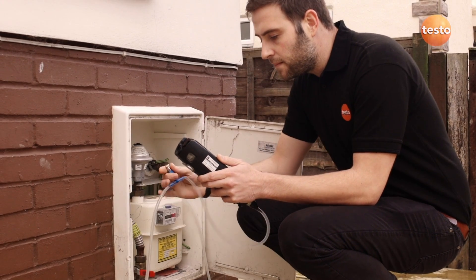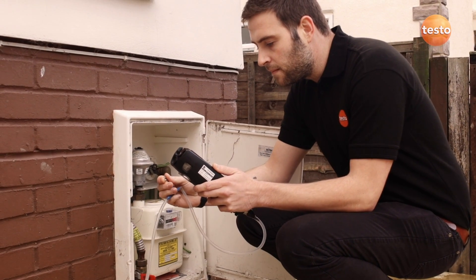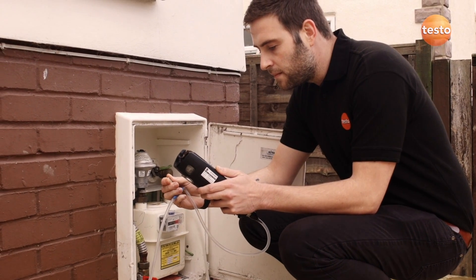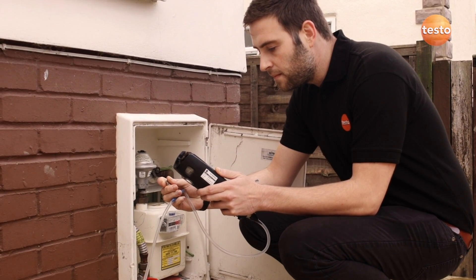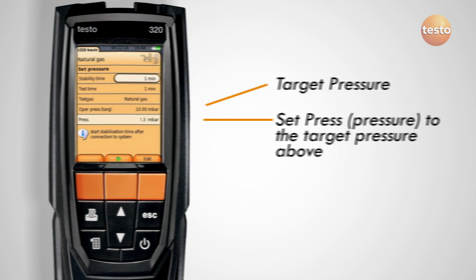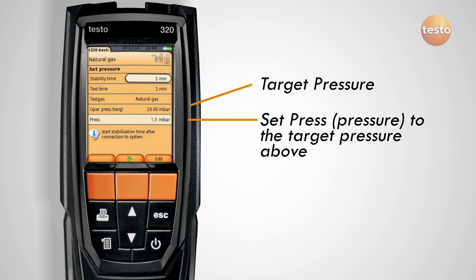Use the blue gas relief valve to reduce the pressure in the system to the target pressure shown on the analyzer. The pressure reading on the bottom line needs to be set to the target pressure shown above, in this case 10 mB.